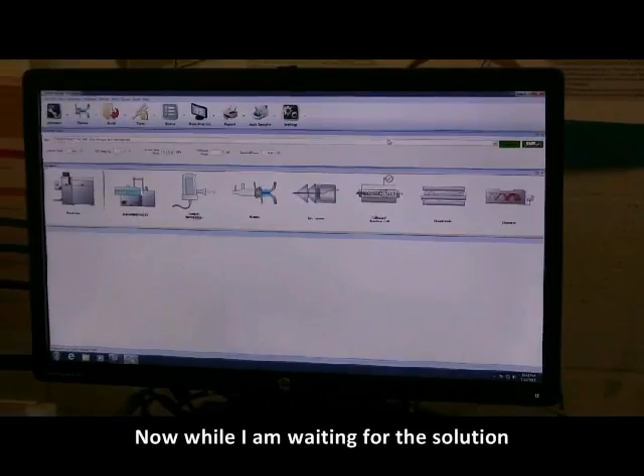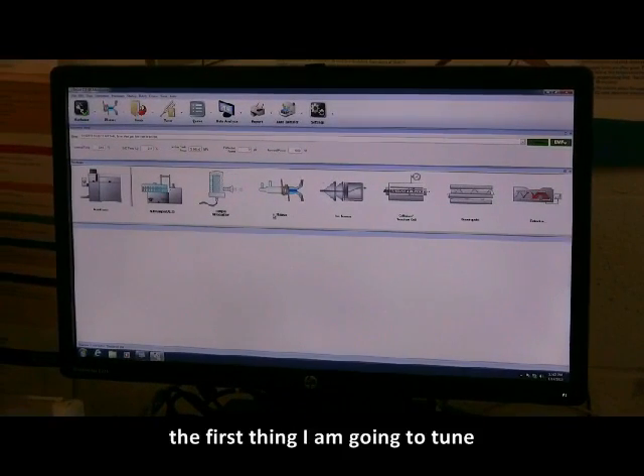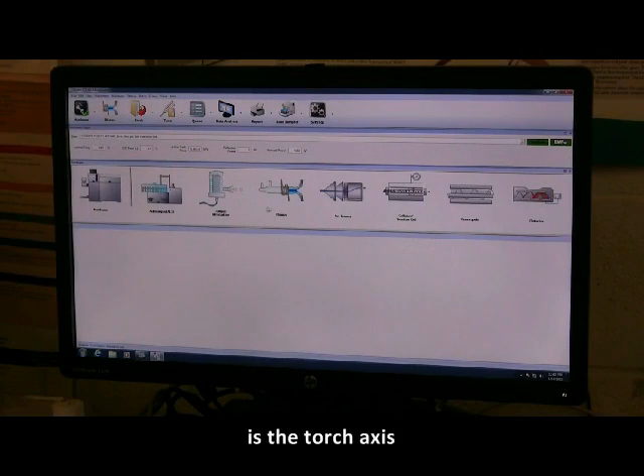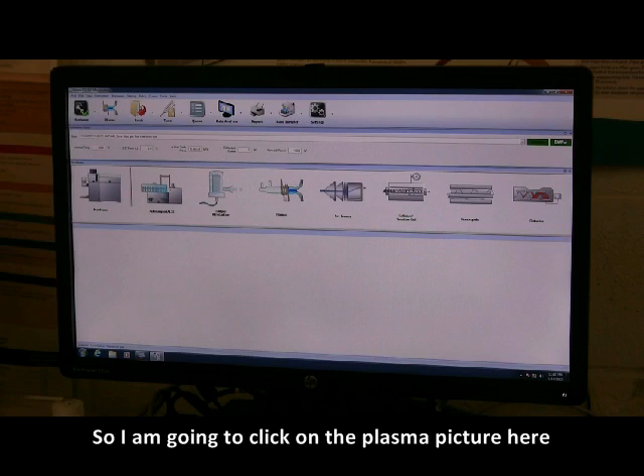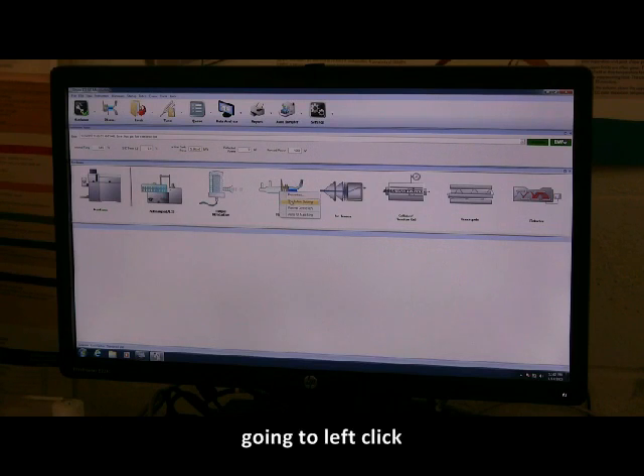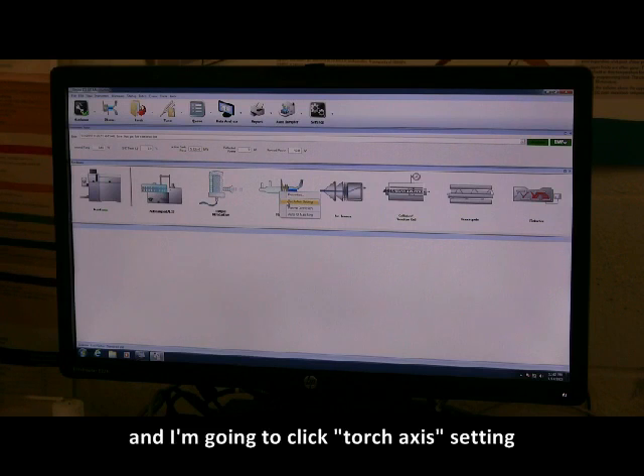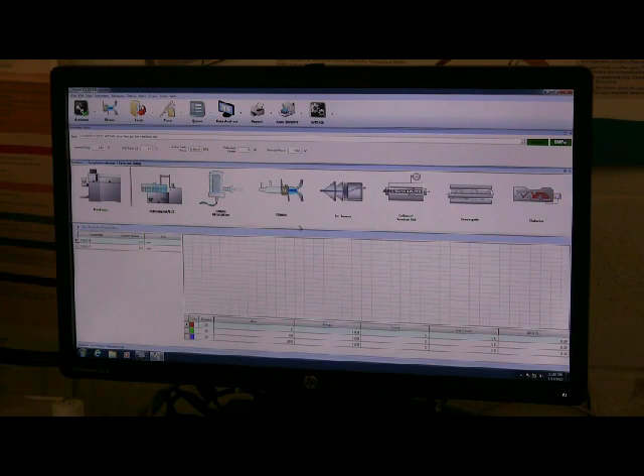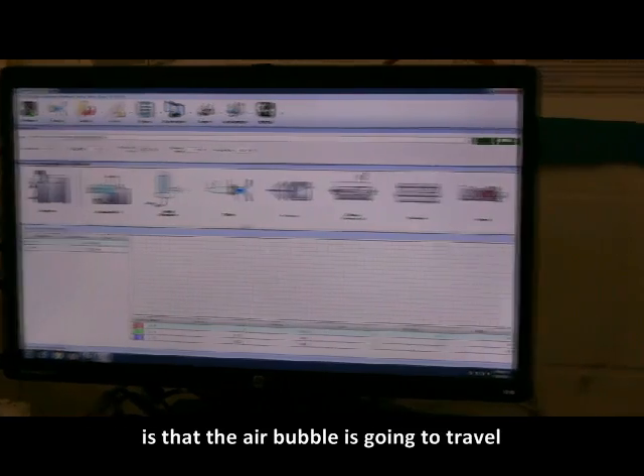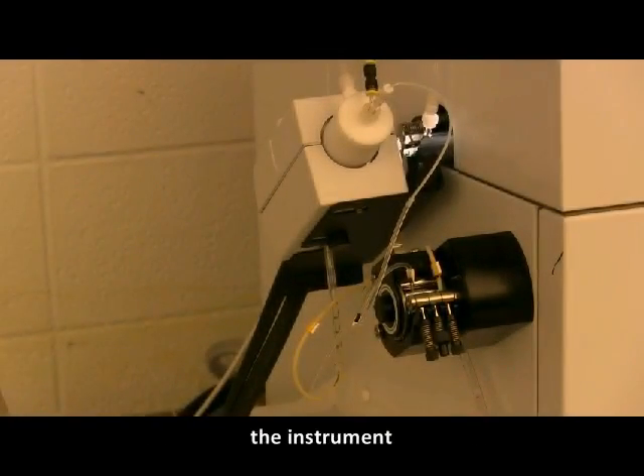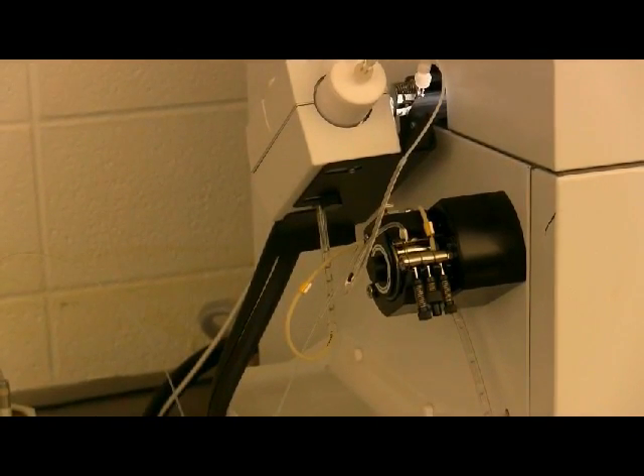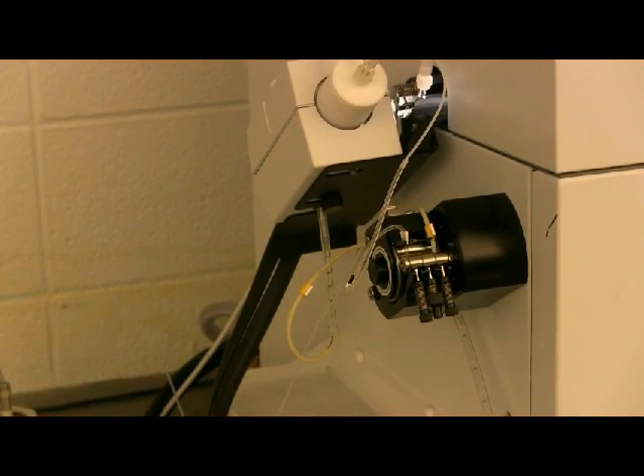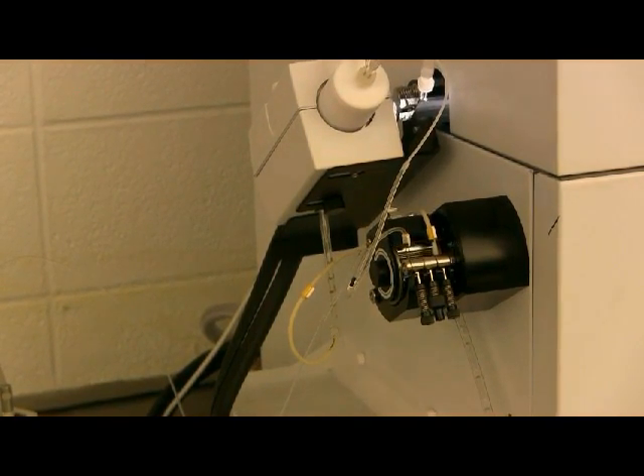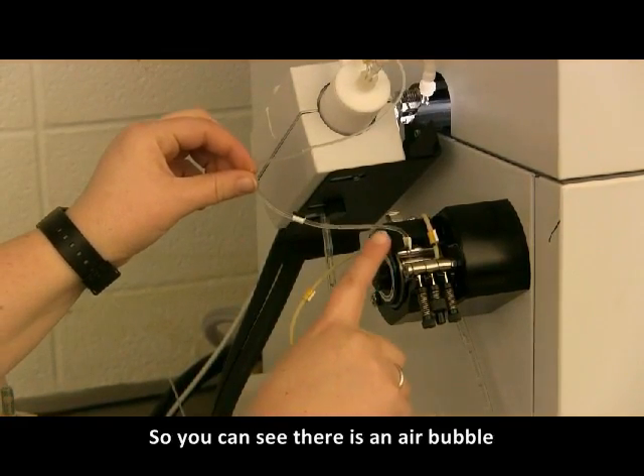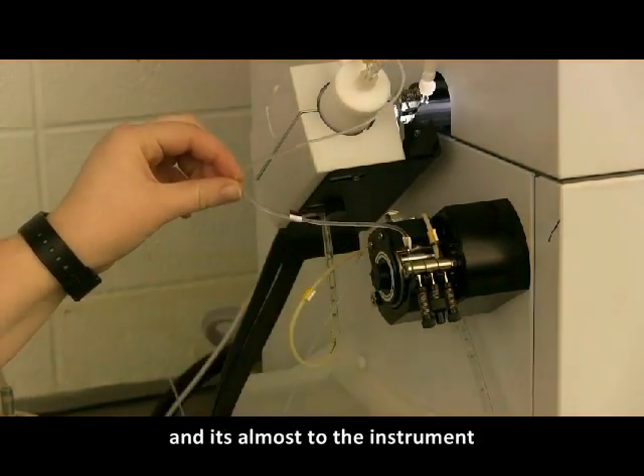While I'm waiting for the solution to get into the instrument, the first thing that I'm going to tune is the torch axis. On the plasma picture here, I'm going to left click, and I'm going to click torch axis setting. Now you'll just have to wait about maybe 30 to 60 seconds, and what you'll see is that the air bubble is going to travel through the peri pump tubing and into the instrument. You can see there's an air bubble here that's passing through the tubing, and it's almost to the instrument.